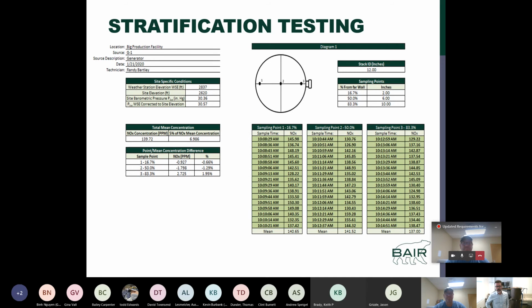So we positioned a probe at 2 inches from the far wall, right in the middle of the stack, and then 2 inches from the near wall. Got our sampling time and sampled for 2 times the response time, and found out what our average concentration was. And then at each point, we would need to be within 5% of that average. So the average concentration was roughly 140 ppm. To be within 5%, we had to be just under 7 ppm at each point, no further from that point.